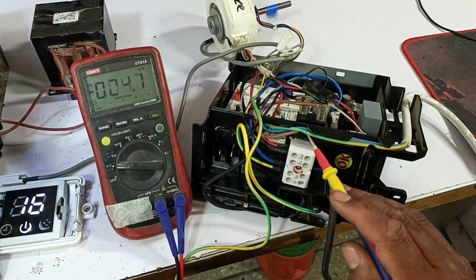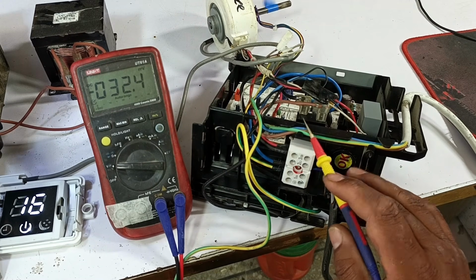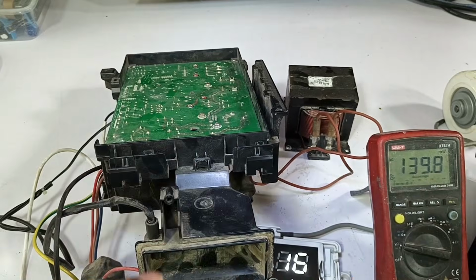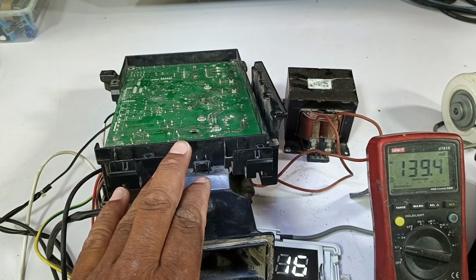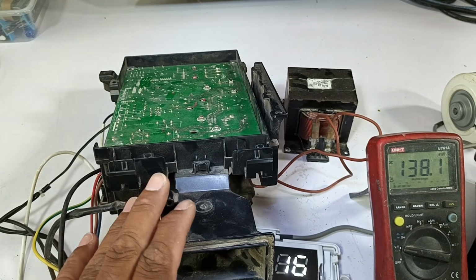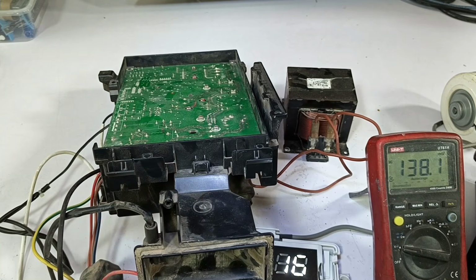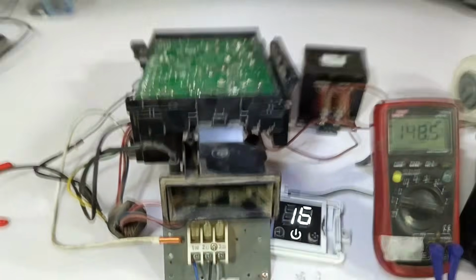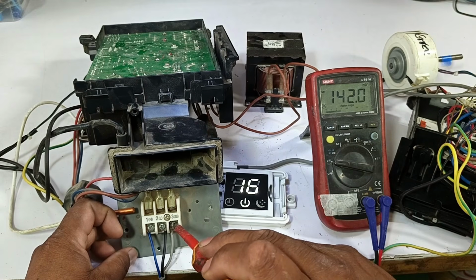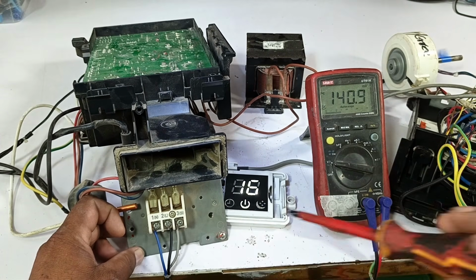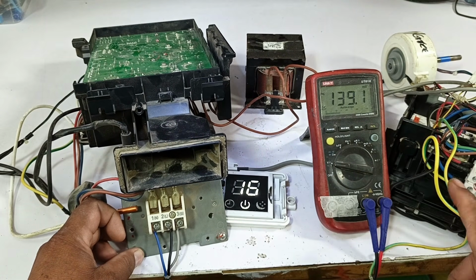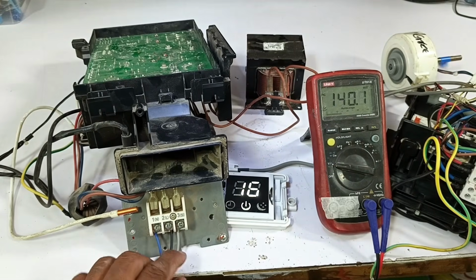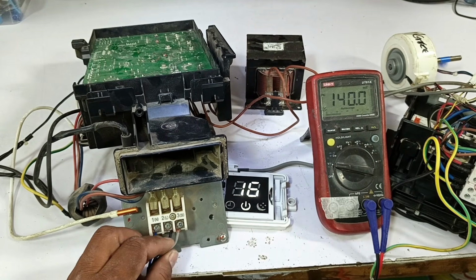We will have to see from which PCB these voltages are coming, because this depends on the design. So here we need to check whether the indoor is generating 25 DC volts, or the outdoor is generating it, or if both are generating it, or if one is generating less and the other is generating more. So for this, what we will do is disconnect this signal wire from one side, whether from the indoor or the outdoor. It's the same thing. So we have disconnected it.